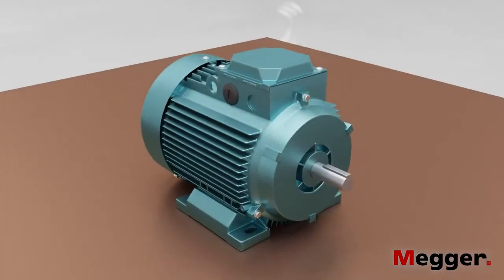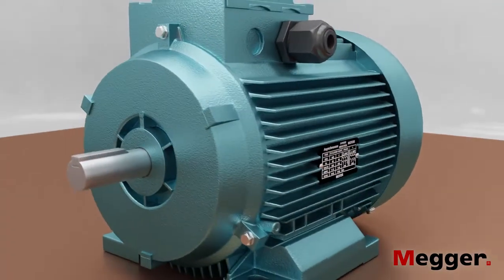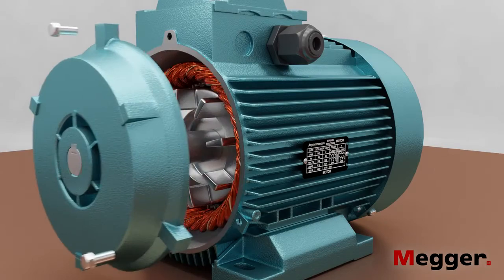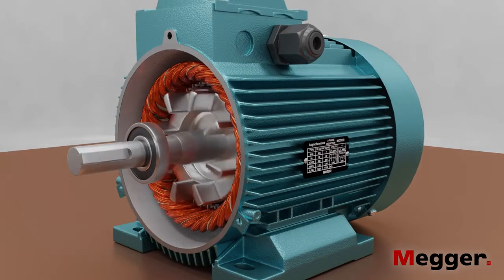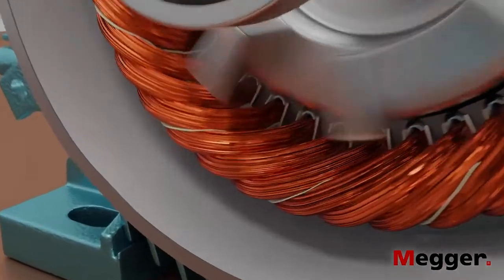So, for example, on startup, when you start the motor and it sees high voltage, you could have a weakness that develops very easily over time in your copper windings. And that will show up as arcing in one of the tests, the surge test, when you perform these routine maintenance tests, maybe once a year, maybe twice a year, whatever the situation might call for. But the whole point is you can detect that problem, and then the voltage settles down at operating or steady state voltage, and the motor runs fine. And that problem never shows up in the operation of the motor. It'll last for months and months like this on a normal operating motor.